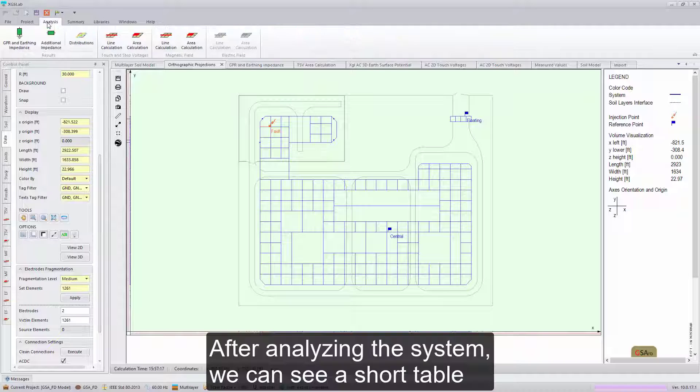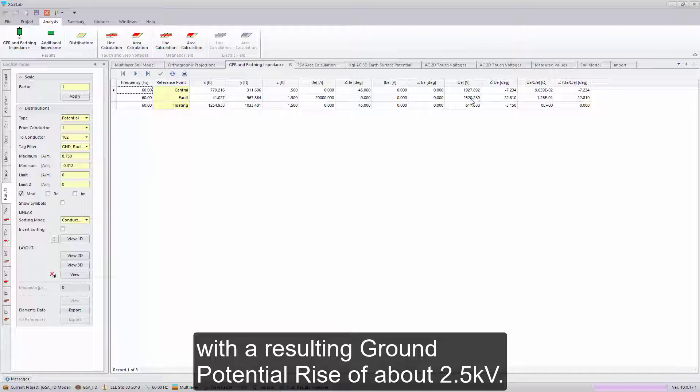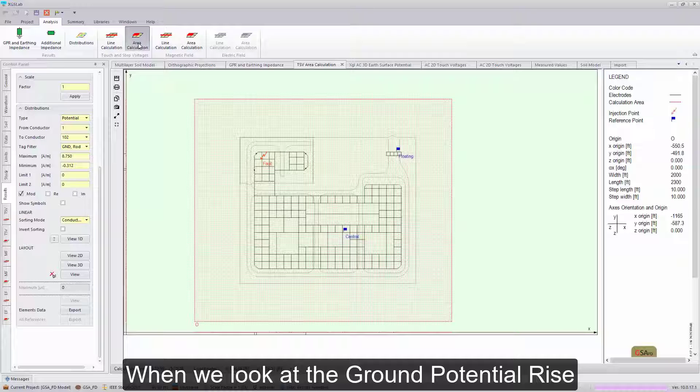After analyzing the system, we can see a short table of our ground potential rise, as well as the system impedance. Here we can see 0.1 ohms with a resulting ground potential rise of about 2.5 kV.